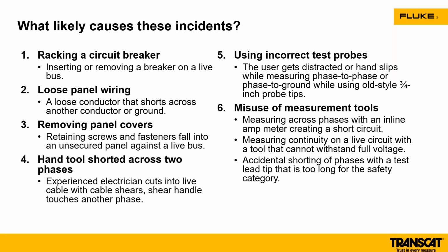Just going in, I've seen incidents where they're coming in and blowing out and cleaning out a connex room, something of that nature. Those loose panel wiring then instantly arc across and cause that fault. Even just removing a panel sometimes, you may have screws or fasteners fall in there, and by removing that panel as well, sometimes you disturb it and the air gets in there, and then again, move something around that causes that to happen. I've literally seen hand tools shorted across it. They put their tools up above, they're working in that cabinet, and the screwdriver or something falls, comes across the two phases, and that's where we can see that as well.